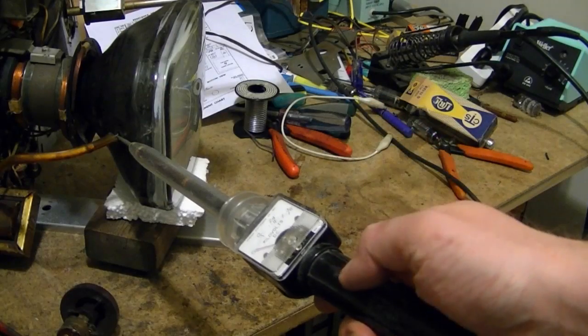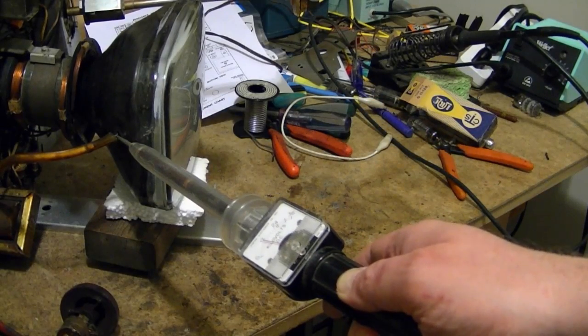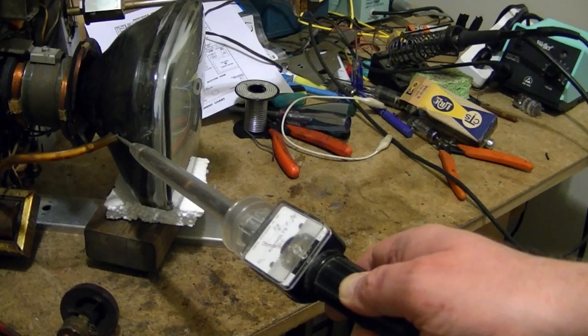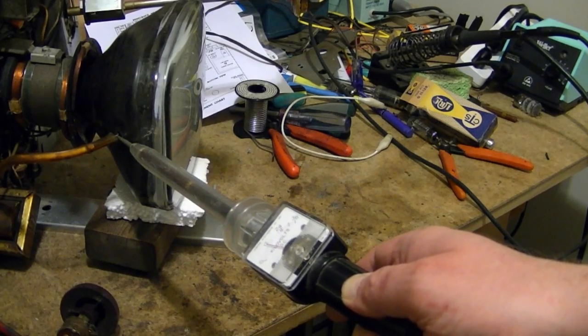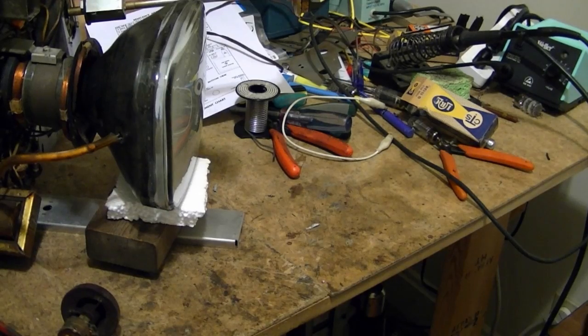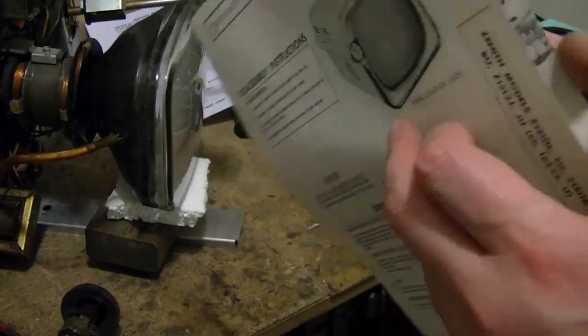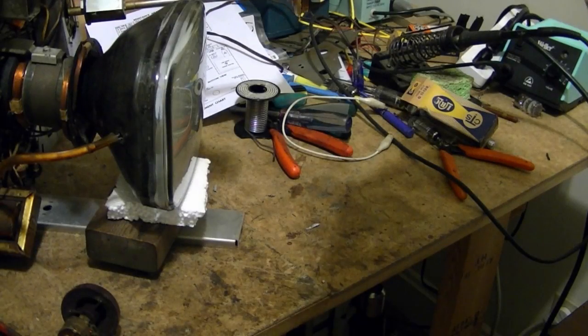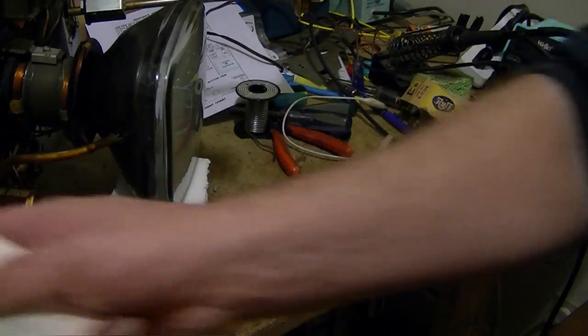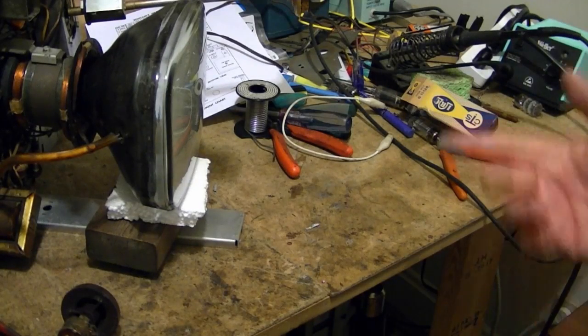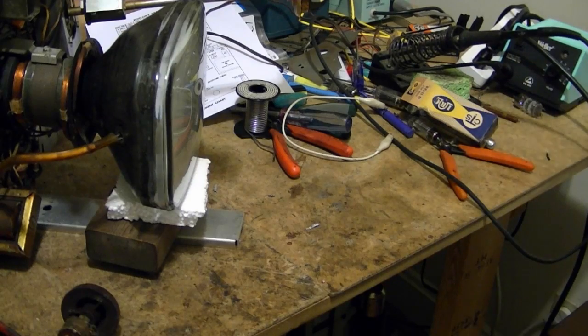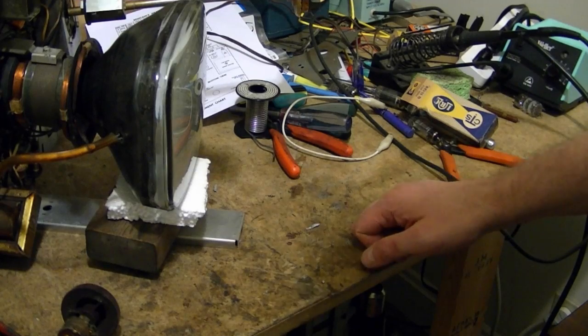Take it off, takes it out of the circuit, turn it on, puts it in the circuit. So I know this meter's off a little bit, so I'm guessing that's about 15,000 volts actually. Which might even be a tad high. Let's see what this says we should have. Yeah, nominally 11 kilovolts, 9.5 to 12.5 is the range there. But it might be a little bit high because this CRT isn't showing anything. If it was conducting, probably drop that high voltage down a little bit.